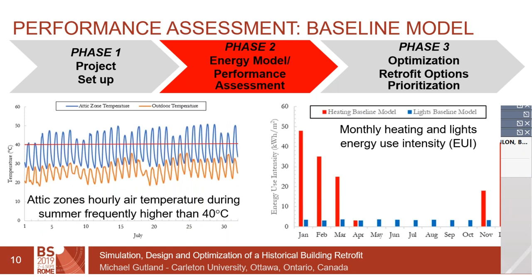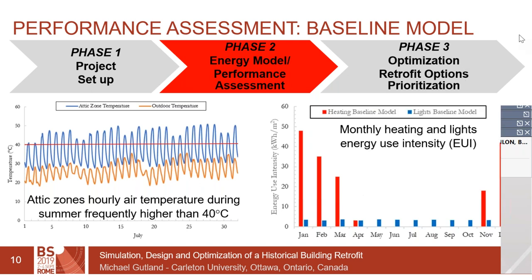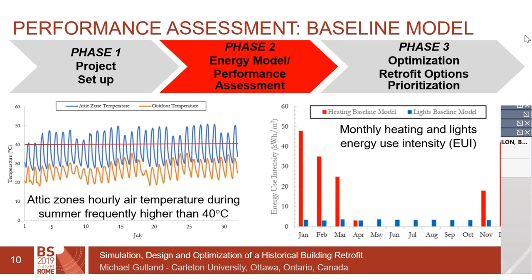Once we had a working model we examined what the results were telling us: what areas of concern are there, and is our model realistic for a building of this typology in this climate? This was compounded by the fact that we were given no measured data — such as annual heating loads or typical indoor climate. One of the first things we looked at was indoor temperatures. Our preliminary model was returning temperatures inside the attic upwards of 40 degrees Celsius in mid-summer, which is obviously uncomfortable. There was a large diurnal spike in the model temperatures.